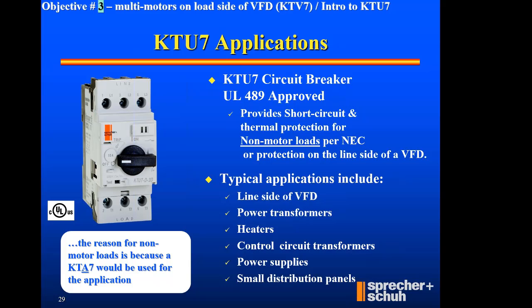That's why I threw KTU in this section, talking about VFDs, where previously KTV7 took care of the load side. KTU7 is certainly a recommended device for the line side because of the short circuit reaction time of a KTU7. KTU7 is going to see a short circuit in milliseconds, as opposed to a molded case circuit breaker, which is going to see it in seconds. So the amount of damage that could occur between milliseconds and seconds, hey, use a better device for the line side of the VFD.